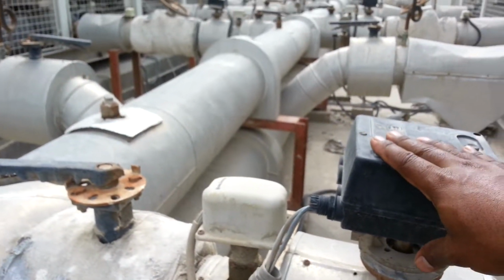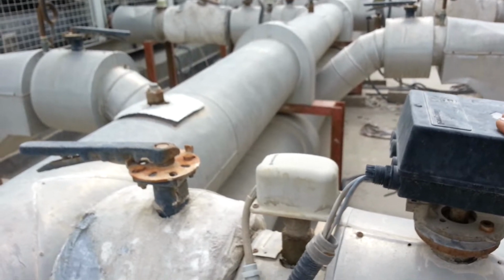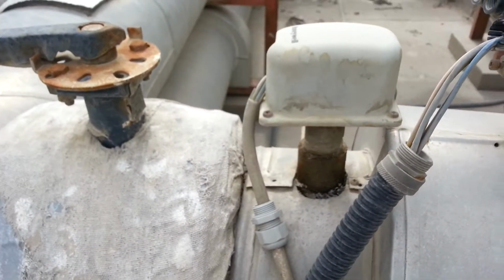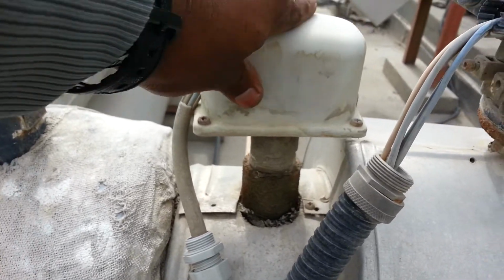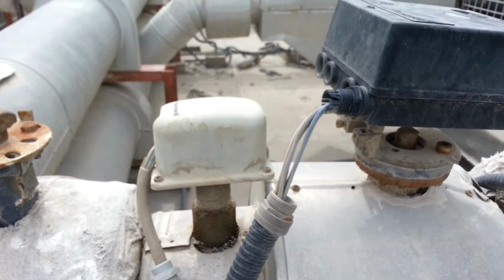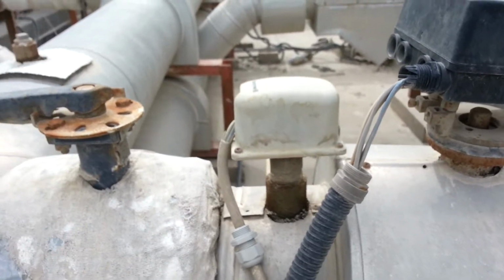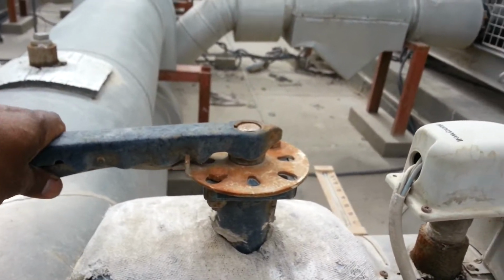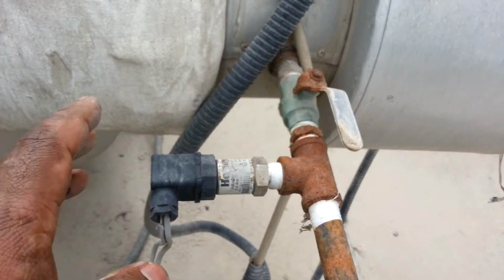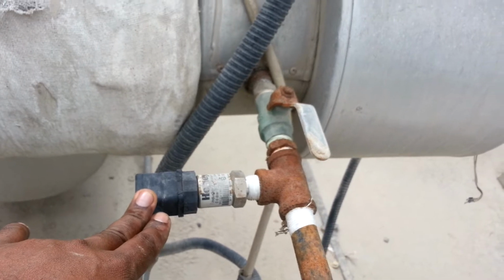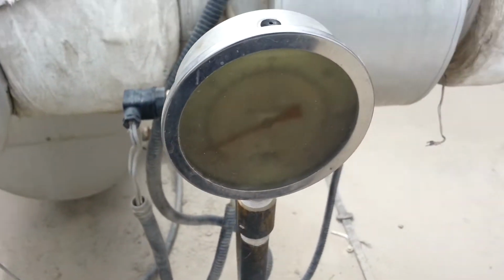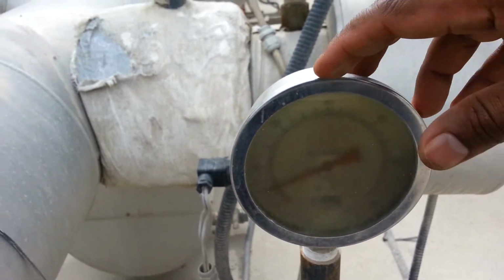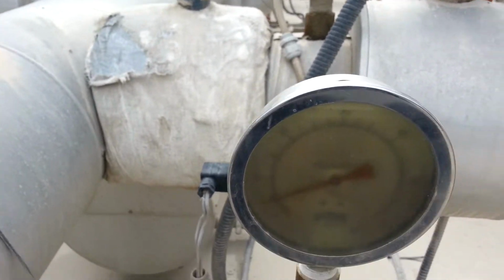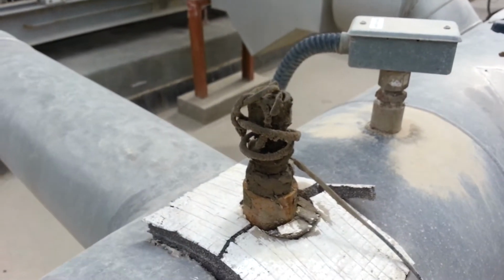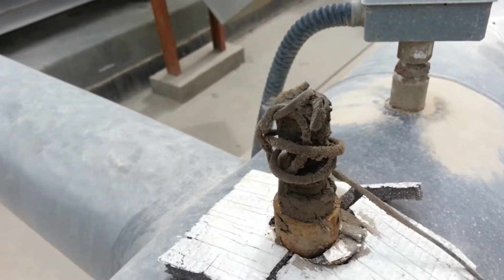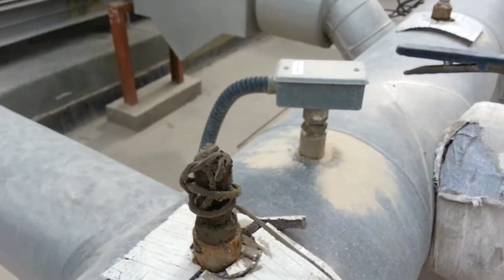And there is an actuator, a Honeywell motorized butterfly valve or actuator. Here there is another flow switch. This is for the main controller fixed in the chiller. And here there is a butterfly valve, and here you can see there is a transducer. This is for BMS. And here there is a gauge. You can see the water pressure, and this is another sensor, and this one senses the water temperature of the main line. This is the main chilled water line.